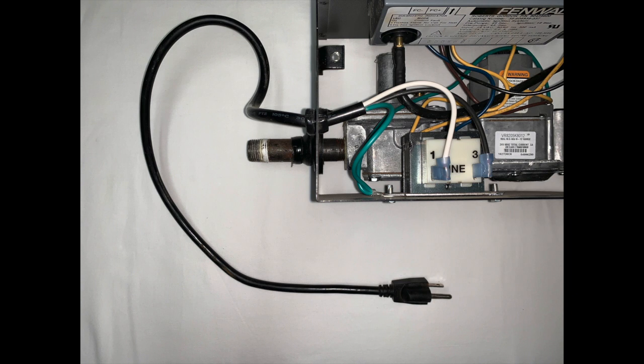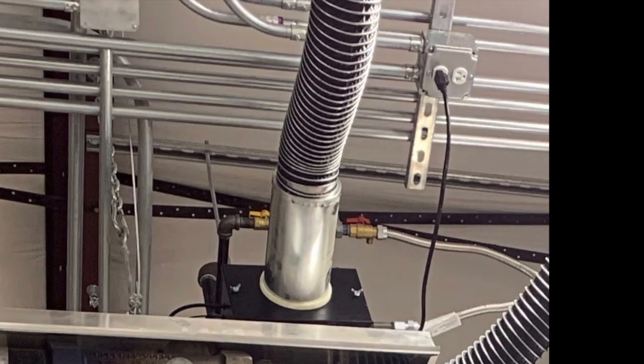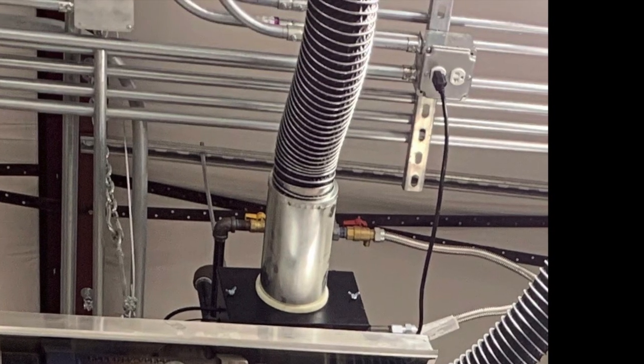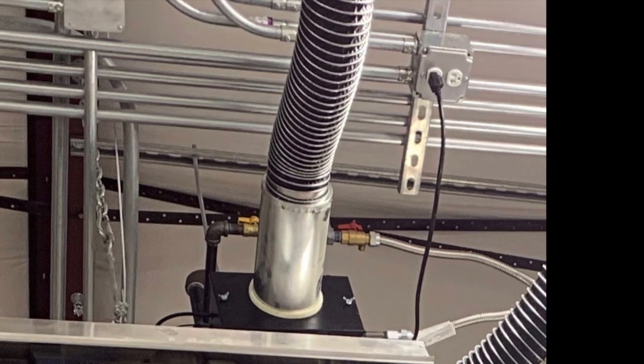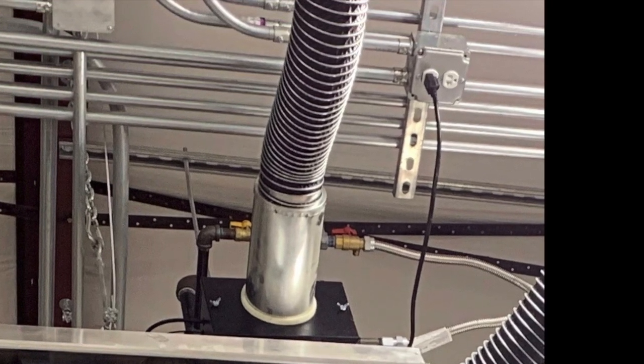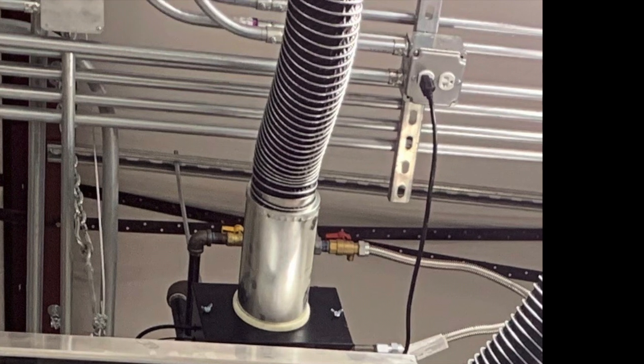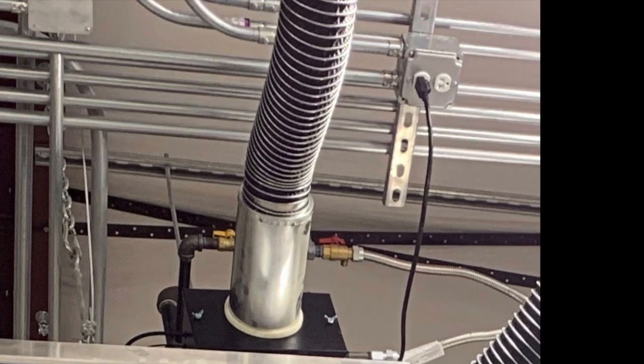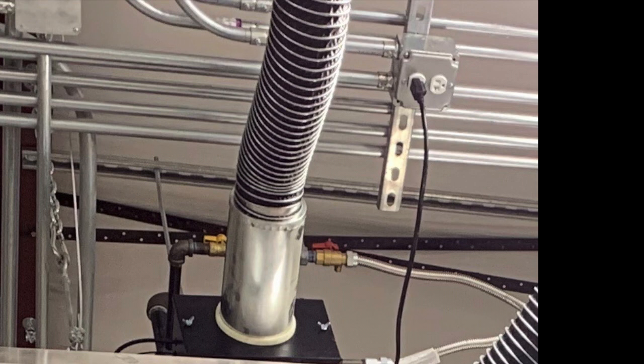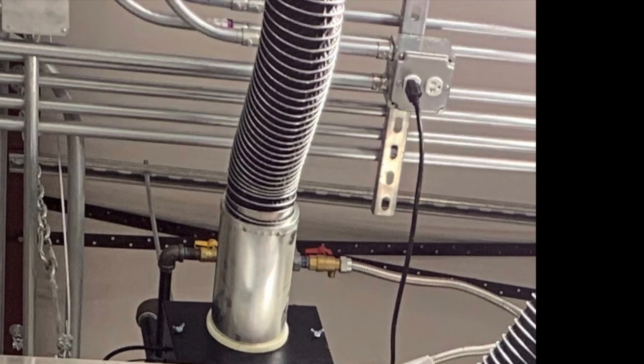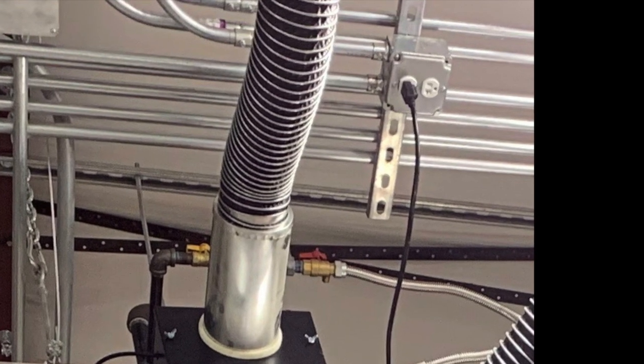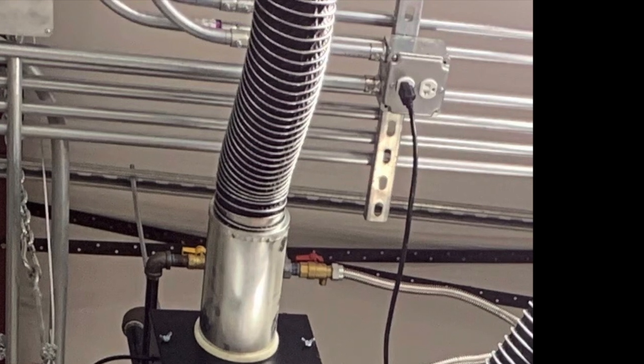Burners are supplied with a U-ground pigtail. We want to use this for a service disconnect. If we need to make it a little longer, not a big deal. The easiest way to achieve this is with a strain relief at the junction box up above. Then SO cord may be zip tied to the burner hanger chain with a female U-ground plug cord end. Again, these heating systems can expand, so slackening the power wiring is a must at the burner.